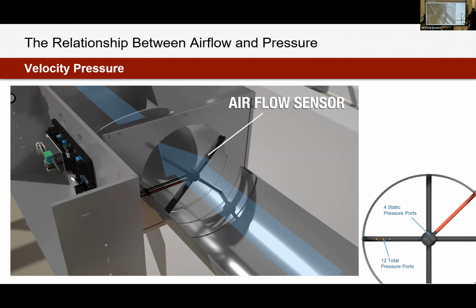But what it allows the pressure to do, we're collecting through 12 different ports. All of those pressure measurements and readings are going to eventually find their way into this center chamber, and they will all average together. The average is what's actually getting sent out to the controller.